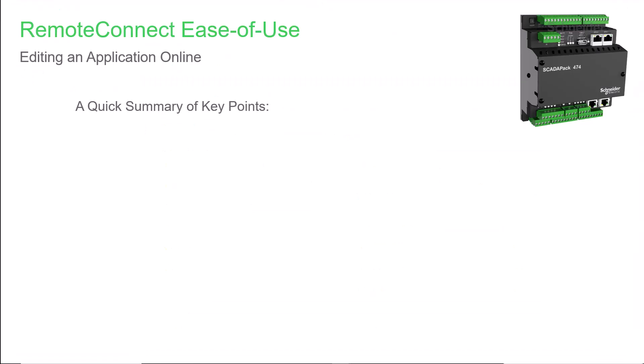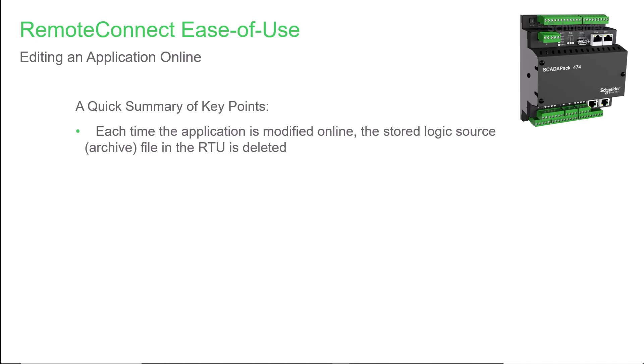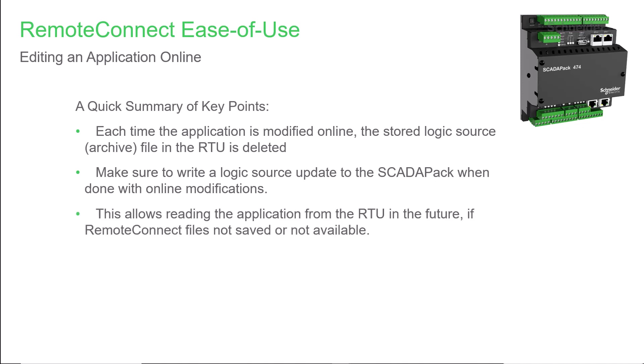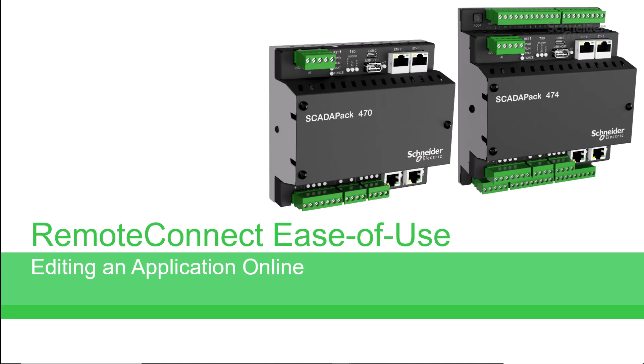Just before closing, here are a few points to remember. Every time either the RemoteConnect configuration or the logic is modified online, the stored logic source or archive file in the RTU is deleted. So it's a good idea to write the logic source file to the SCADAPack when you're done with online modifications. This allows reading the application from the RTU later if for any reason the RemoteConnect application files are not available. Still, remember to save the RemoteConnect files and store them in a location where they can be found when needed again. To learn more about the SCADAPack, access the user documentation on the Schneider Electric Exchange Shop and Schneider Electric website. Also, see our videos on YouTube.